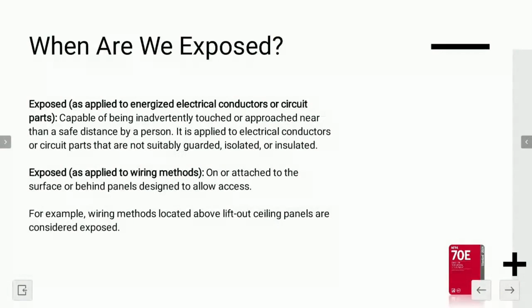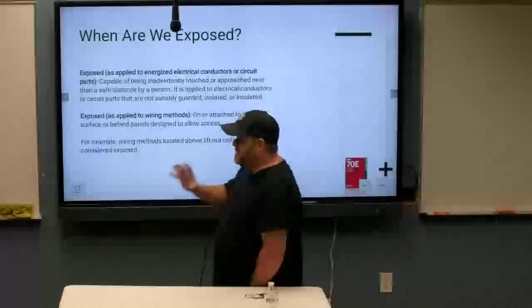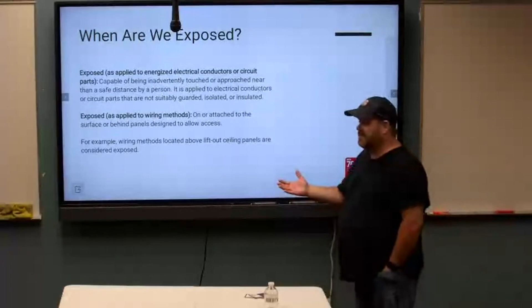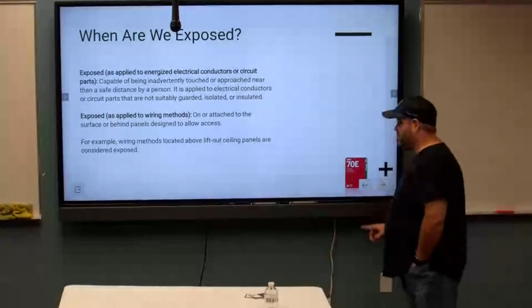Okay. Now, I always tell people you have to ask yourself, even after you've performed lockout tagout, am I exposed to any stored energy? So what does exposed mean? I'm glad you asked. The 70E has two definitions for exposed. The first one is capable of being inadvertently touched or approached nearer than a safe distance by a person. It's applied to electrical conductors or circuit parts that are not suitably guarded, isolated, or insulated, or on or attached to the surface or behind panels designed to allow access. So if you could accidentally make contact or even approach too close to an energized circuit part or conductor, are you exposed? Yeah, good answer. Yes, you're exposed.